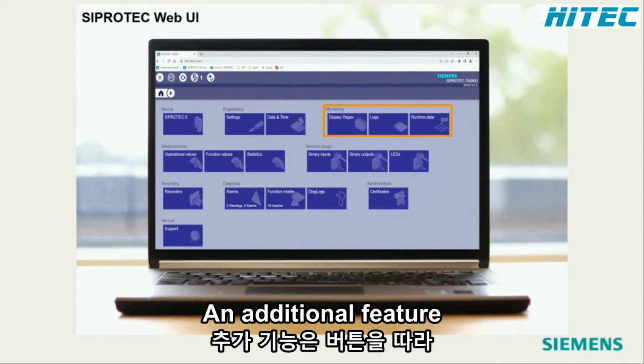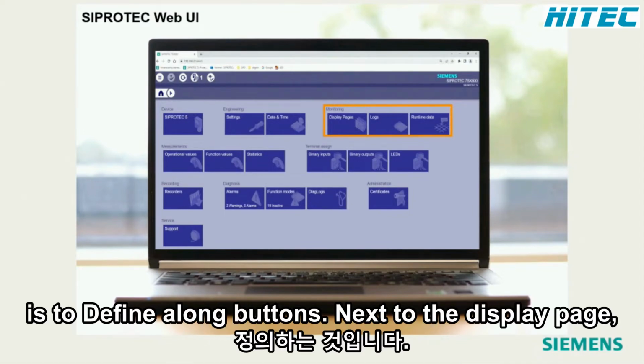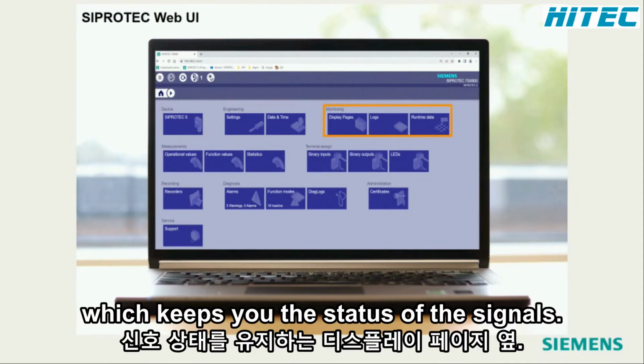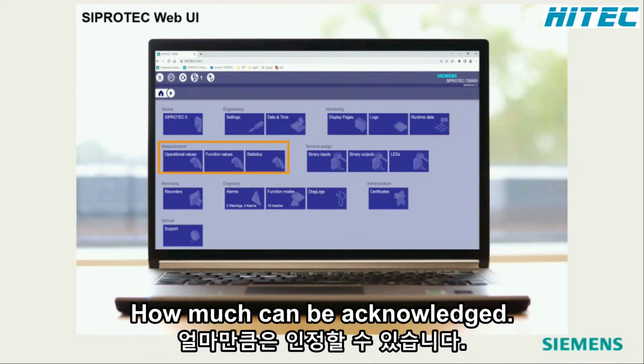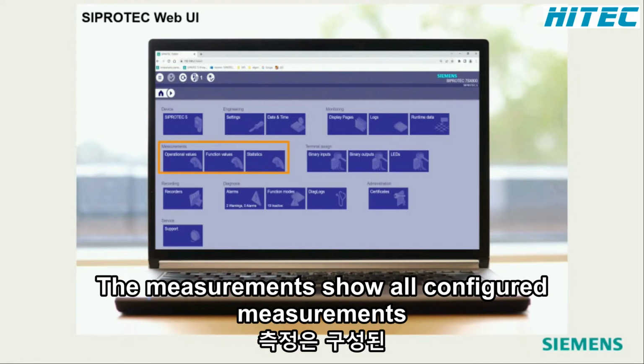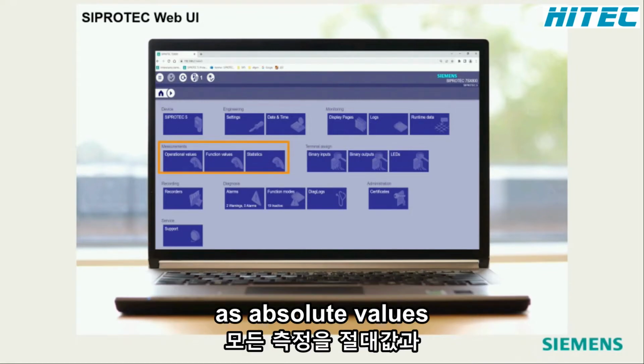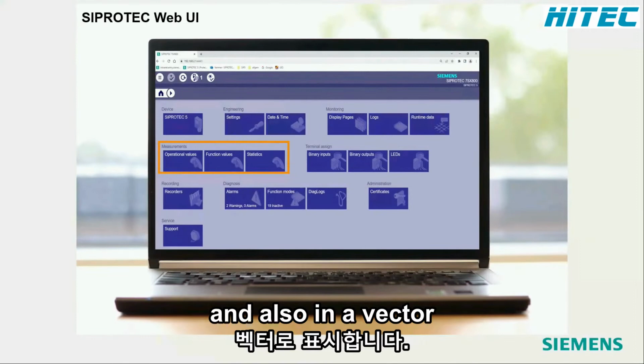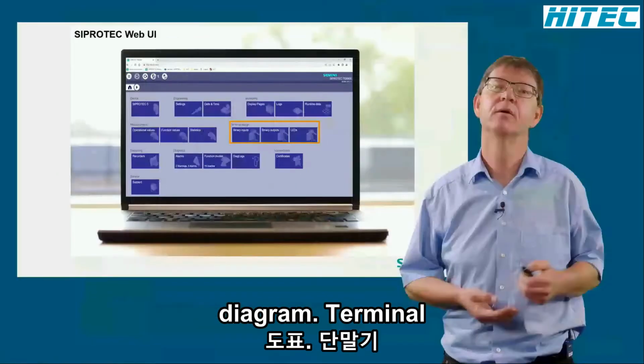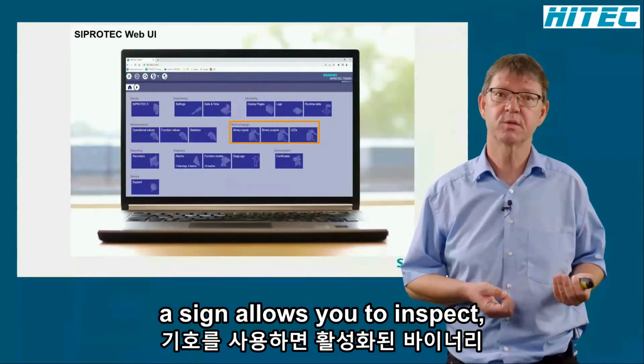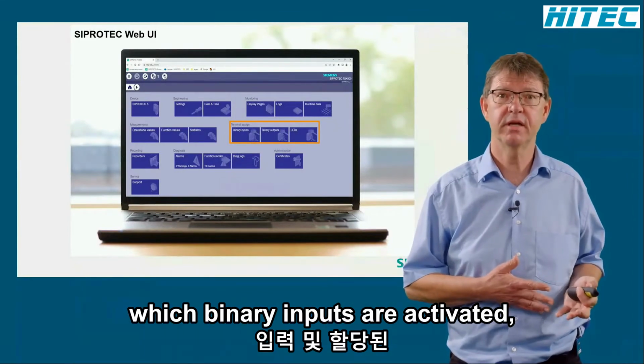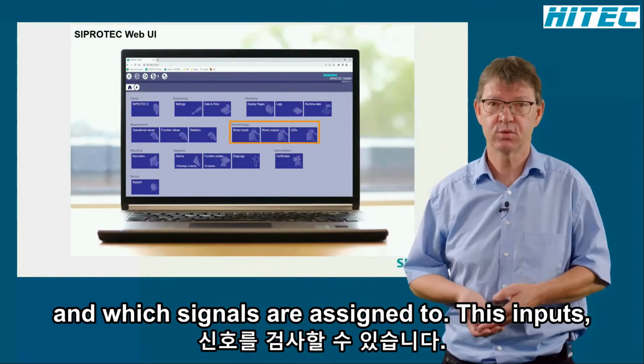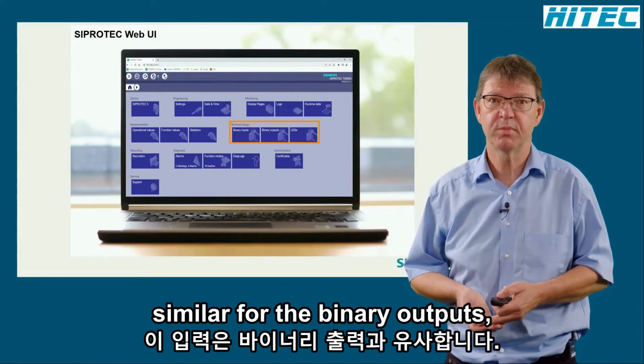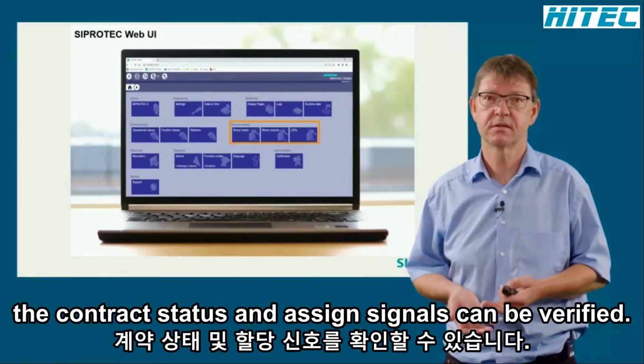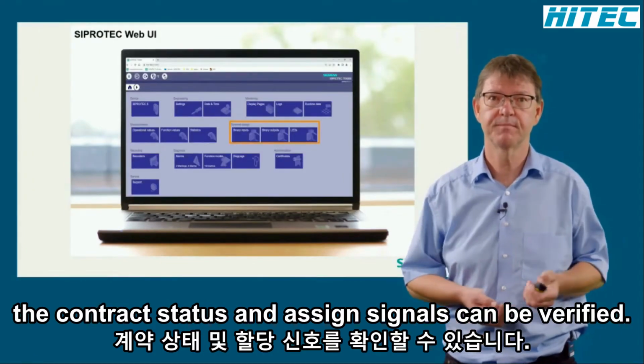An additional feature is to define alarm buttons next to the display page, which gives you the status of these signals and which can be acknowledged. The measurements show all configured measurements as absolute values and also in a vector diagram. Terminal Assign allows you to inspect which binary inputs are activated and which signals are assigned to these inputs. Similar for the binary outputs, the contact status and assigned signals can be verified.